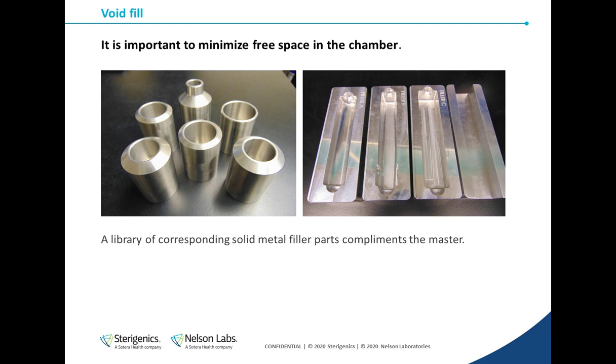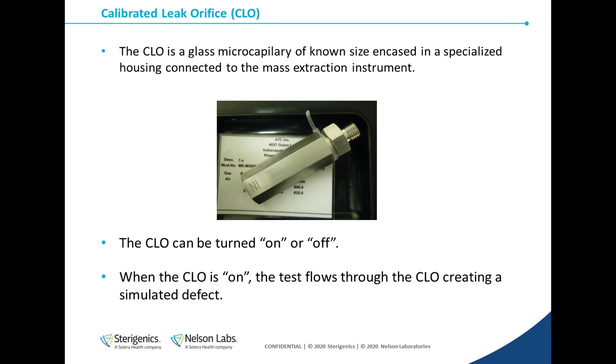Finally, we need some void fill. Free space in the chamber will affect the test, so we want to minimize free space as much as possible. These void fill parts are also solid metal, so they have no leaks. We have a variety of different filler options for each chamber, so we can use a variety of sample sizes with each chamber. The CLO is a calibrated leak orifice.